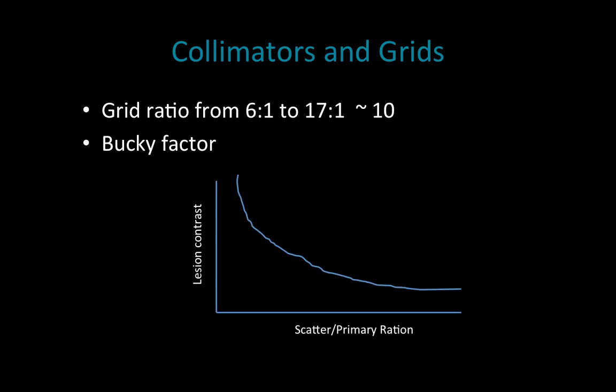For example, looking at the scatter-to-primary (S/P) ratio versus lesion contrast: with a low scatter-to-primary ratio — meaning scatter is low — we have great lesion contrast. However, as scatter increases and our ratio increases, our image contrast decreases. It's a sigmoidal curve: as we increase scatter, lesion contrast decreases. That's the whole reason why we use grids in some of our imaging.